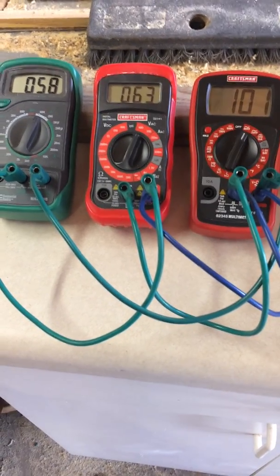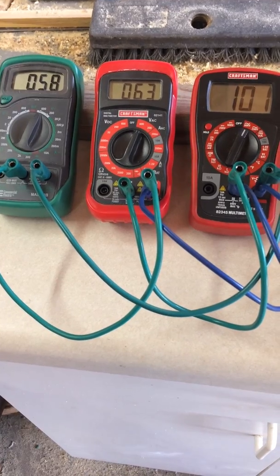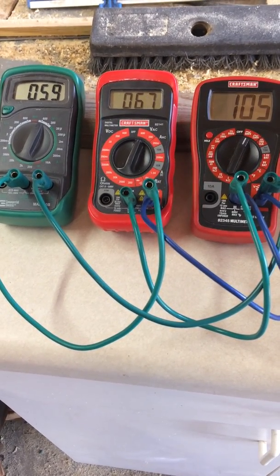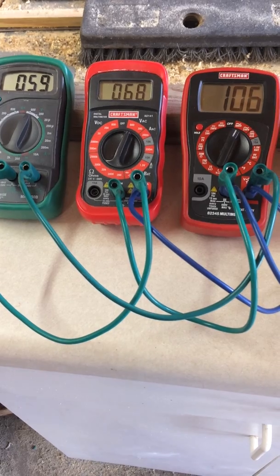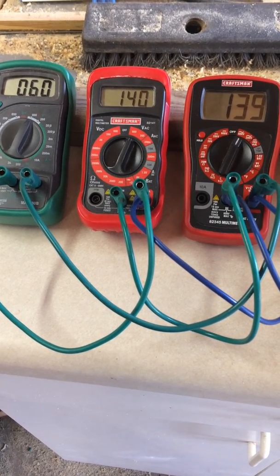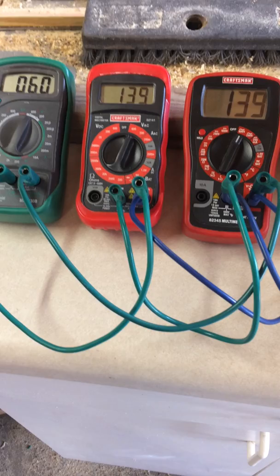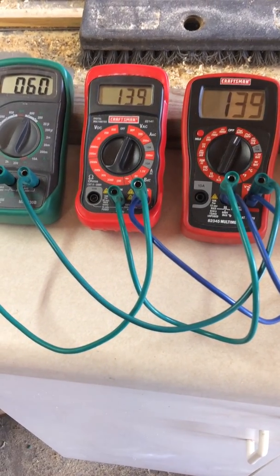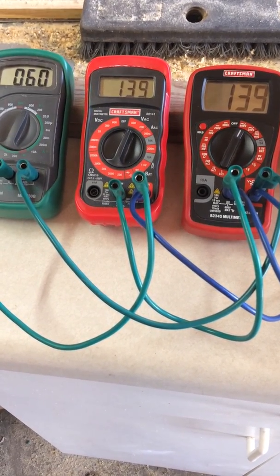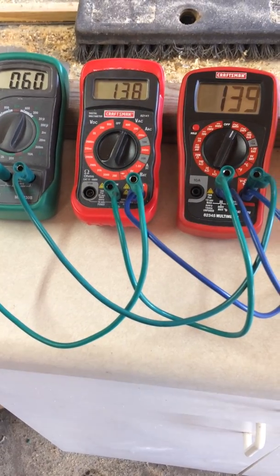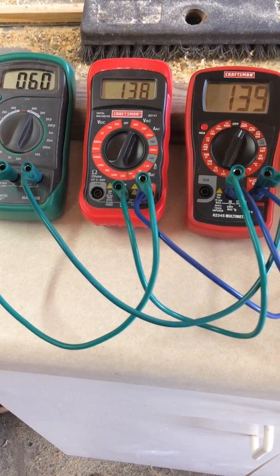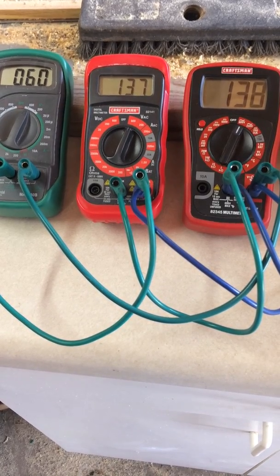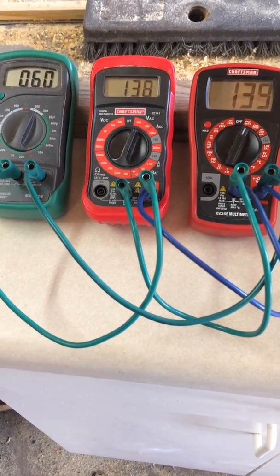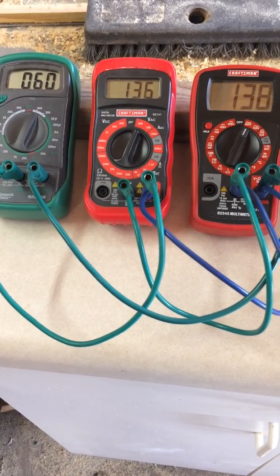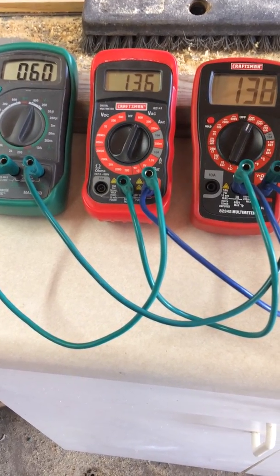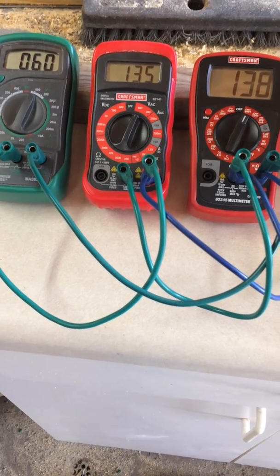But you hit a certain point, and it's really not something we can calculate. And all of a sudden, the capacitor and motor start transferring energy back and forth. And if this was a real situation with a pad mount transformer and underground feeders, we could exceed the voltage on those underground feeders, and at some point we might see a failure on that as well. And this would all come about because one of the overcurrent devices had tripped open on the three-phase feeder. So again, a demonstration of series resonance.